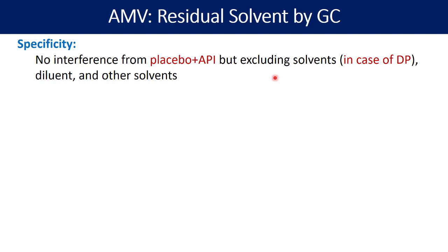However, you must avoid adding the solvent you are going to quantify. For example, if ethanol is the solvent used for paracetamol tablet manufacturing, then you must exclude ethanol from this placebo preparation. In case of a simple API where you are conducting residual solvent validation, the placebo does not come into the picture — only the diluent is required to assess interference at the retention time of your residual solvent. If you have more than one residual solvent to assess, such as methanol and ethanol, you also have to confirm that these two solvents do not interfere at each other's retention time.